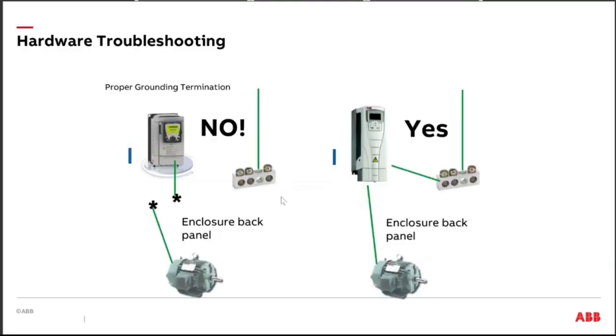When we bring the ground wire back from the motor, this is just kind of for fun. That's an old Altivar 61 or 71 on that left-hand side there. I just did that because I was just goofing a little bit. When we pull our ground wire from our motor back, we want to pull the ground wire in unbroken ground from the motor back up to the drive. And we want to land that on the PE lug of the drive, potential earth, okay?